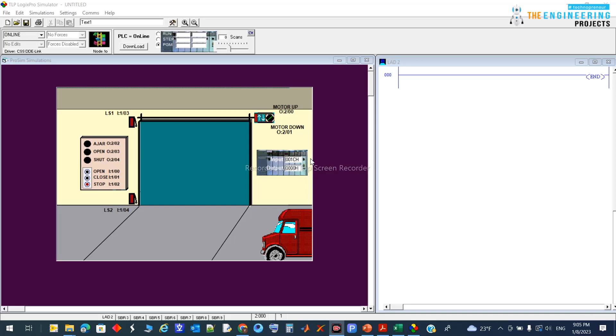As I always say, first list your I/Os then assign addresses. Here you can see: open is input I10, close is I11, stop is I12, limit switches are I13 and I14. For outputs: motor up is Q00, motor down is Q01, and the indicators are Q02, Q03, and Q04.